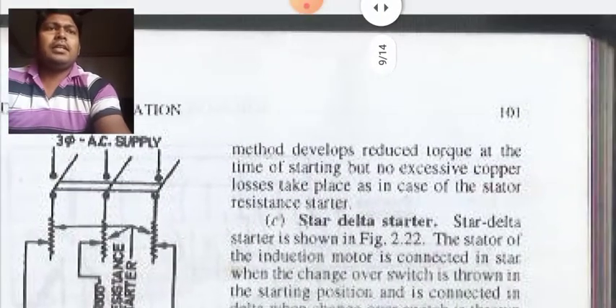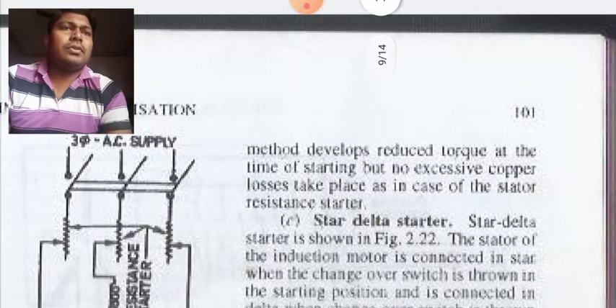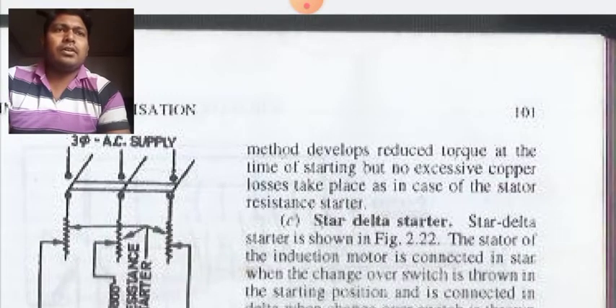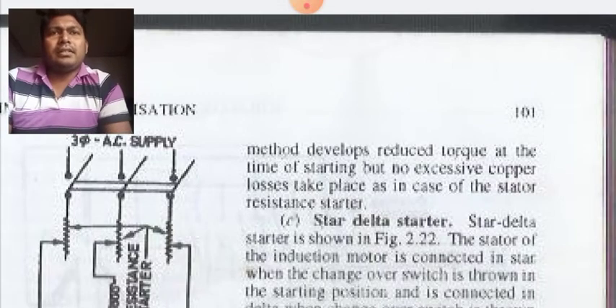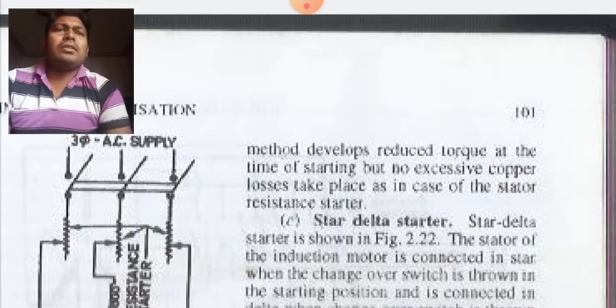This method develops induced or reduced torque at the time of starting, but no excessive copper loss takes place as in the case of stator resistance starter. So this is advantageous as compared to your stator resistance starter. Now let us discuss star delta starter.